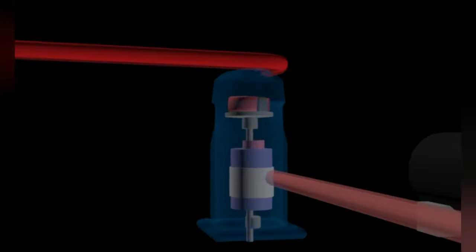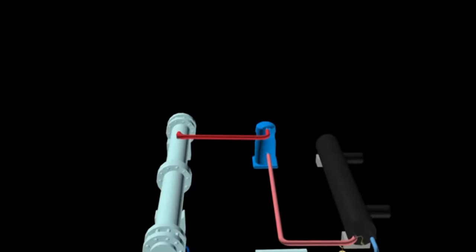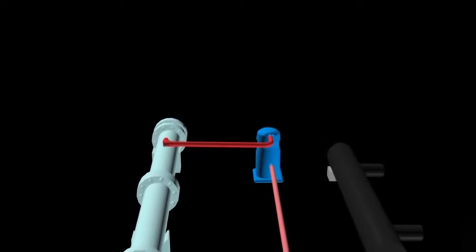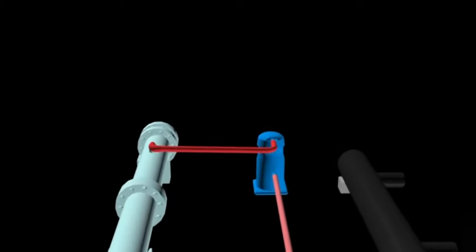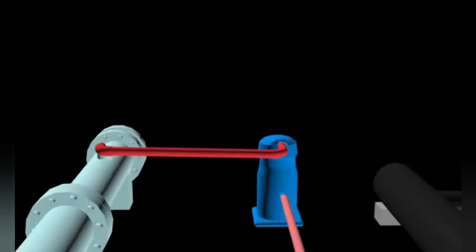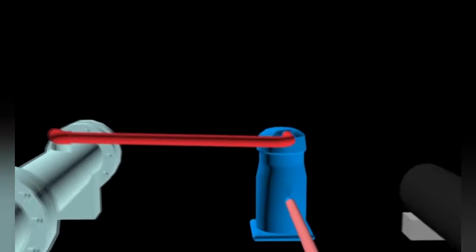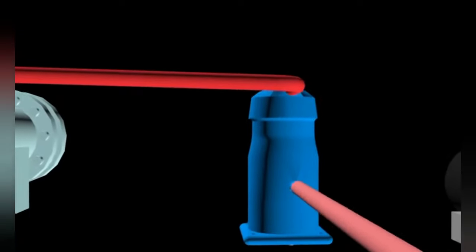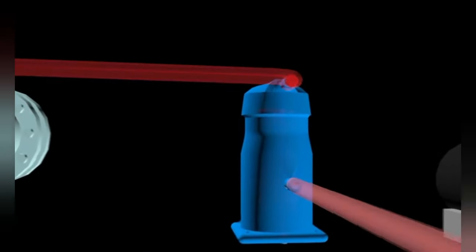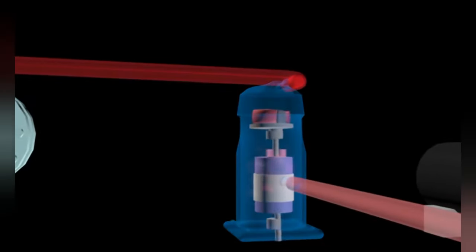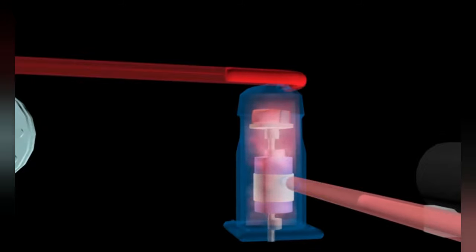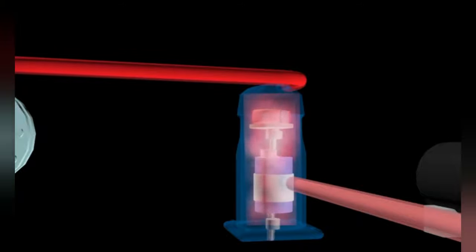The compressor works to increase the pressure of the refrigerant. In addition, it also serves to increase the temperature of the refrigerant higher than the temperature of the condenser water, so that heat transfer can occur in the condenser. The refrigerant enters the compressor as low pressure gas and exits as high pressure gas.